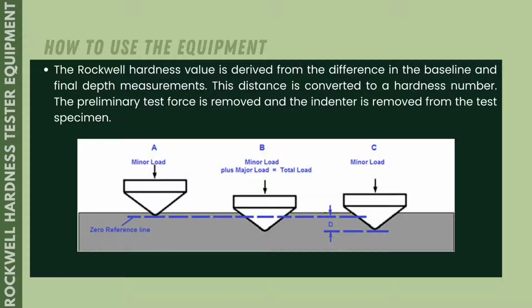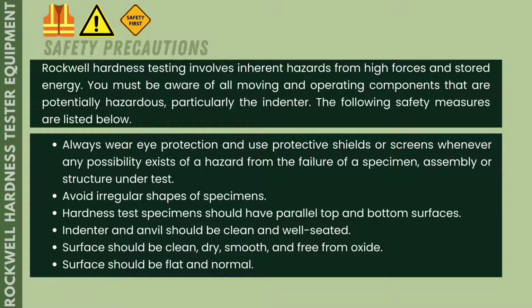The Rockwell hardness value is derived from the difference in the baseline and final depth measure. This distance is converted to a hardness number. The preliminary test force is removed and the indenter is removed from the test specimen. Then you can see in the picture how to use this equipment. So let's come now to the safety precautions to be considered when using a Rockwell hardness tester.